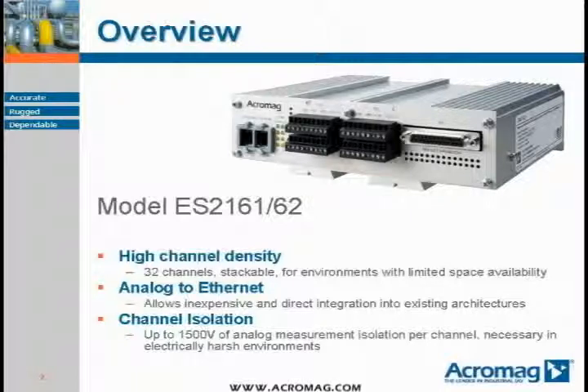allow these units to support DC current, DC voltage, DC millivolts, thermocouples, RTDs, potentiometers, strain gauges, load cells, frequencies, and much more. Also important in the new EtherStax models is the use of differential inputs instead of single-ended inputs with a common ground. Differential inputs can reject up to 10 volts of common mode voltage between channels, eliminating the need for isolators in most applications. If higher common mode voltage rejection is needed on a per-channel basis, the ES2162 voltage input card can be coupled with 8B isolation amplifiers for up to 1500 volts of isolation.